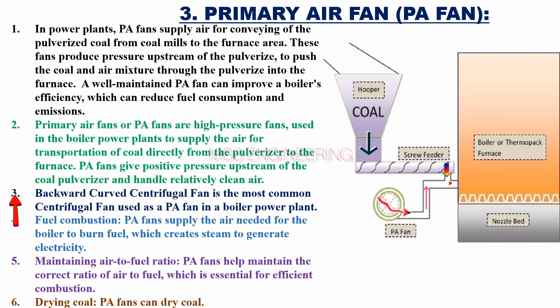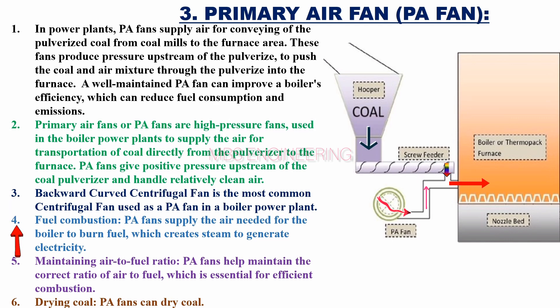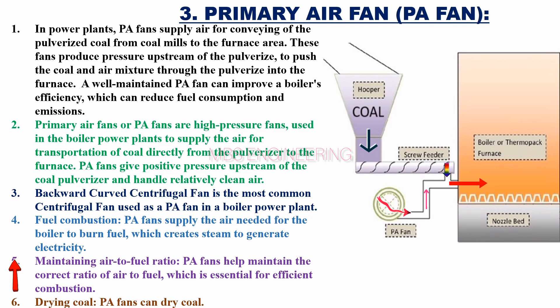The backward curved centrifugal fan is the most common centrifugal fan used as a PA fan in a boiler power plant. PA fans supply the air needed for the boiler to burn fuel, which creates steam to generate electricity. PA fans are also used to maintain the air-to-fuel ratio — they help maintain the correct ratio of air to fuel, which is essential for efficient combustion.